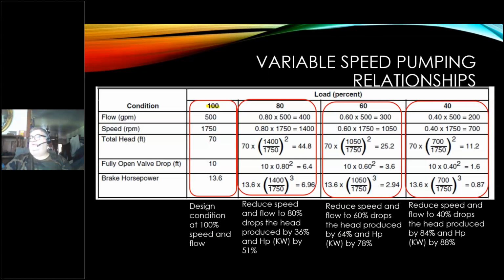Is this practical? I'm going to say no, because you did the calculations, and this is what we came up with as a result. And I doubt it, again. I said that even at zero flow, if you remember a previous slide, no flow at all, we still are somewhere between 10 and 15 horsepower because it's just pumping in itself.